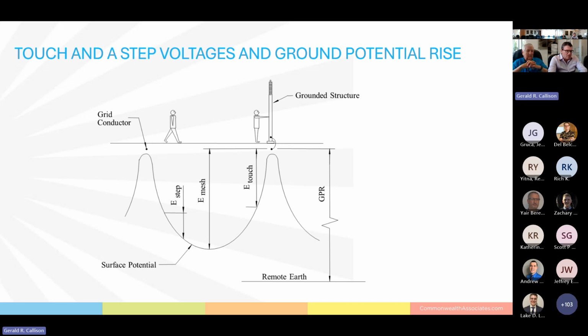A touch potential, however, is a little bit more complicated, but very critical. As current is leaving the ground grid through that grid to soil interface in its path back to its source, creating that ground potential rise, the potential of the ground grid is rising. Now, if you have a grounded structure, like we see here, maybe something like a light pole, maybe a dead tank circuit breaker whose tank is connected through leads to the ground grid, anything that is electrically connected to the ground grid, that is bonded to the ground grid, is going to rise to the GPR. It's going to rise at the same potential as the ground grid is rising. So when this person in this picture is touching this grounded structure, he or she is functionally, electrically touching the ground grid because it's bonded to the ground grid.